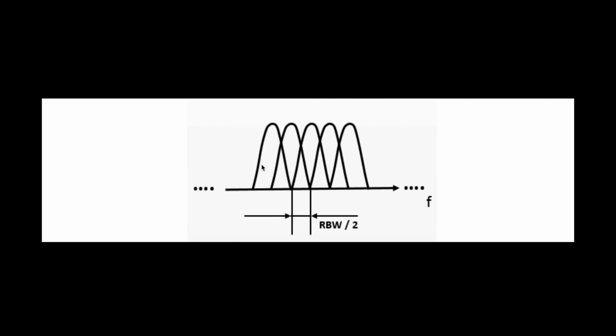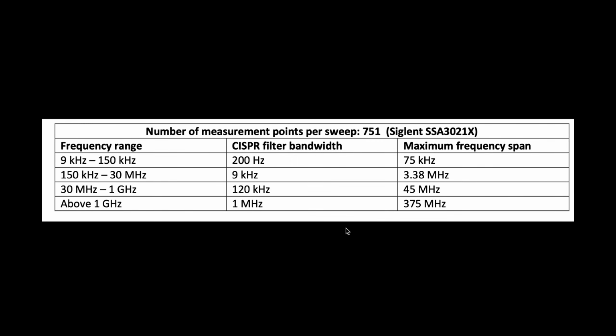So in order to cover the entire frequency spectrum, CISPR 16 defines that the adjacent frequency points shall not be more than half of the resolution bandwidth. So in this case, 9 kilohertz divided by 2 should be 4.5 kilohertz. With this information, as long as we understand our spectrum analyzer model correctly, we can do the math, and it shows in this table based on the model that I have. For the conducted emission test from 150 kilohertz to 30 megahertz, we will need to split the entire spectrum into at least 9 segments with a span of 3.38 megahertz.